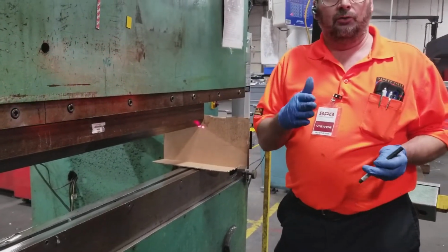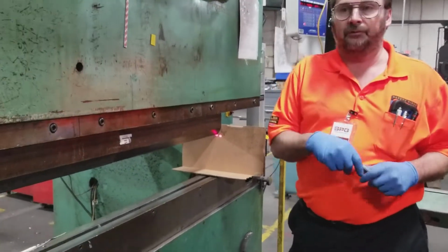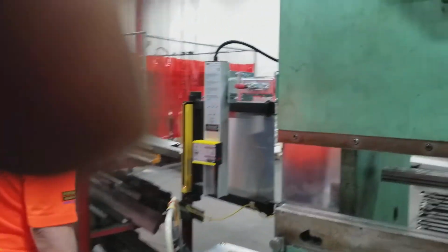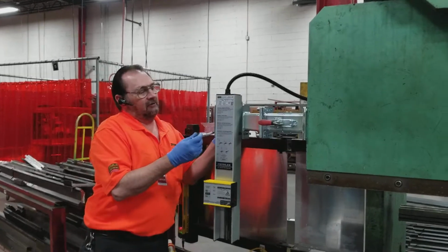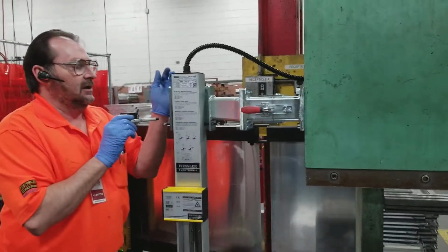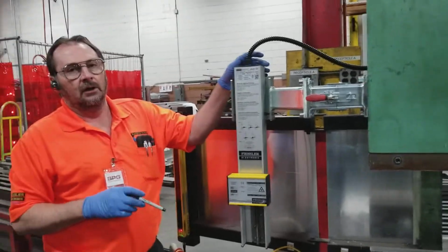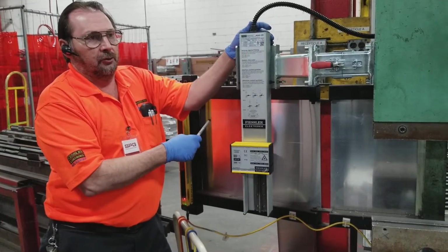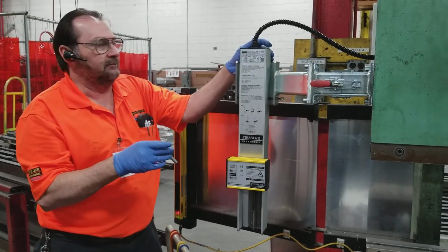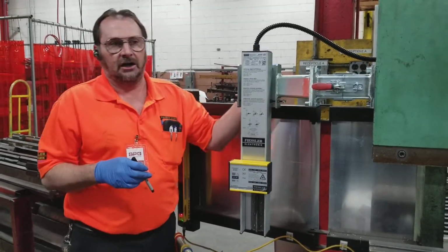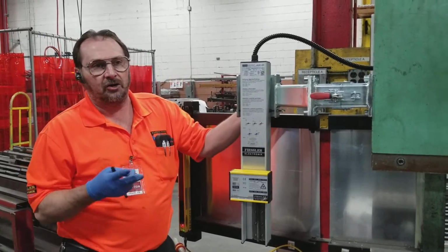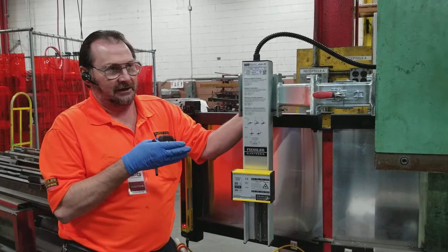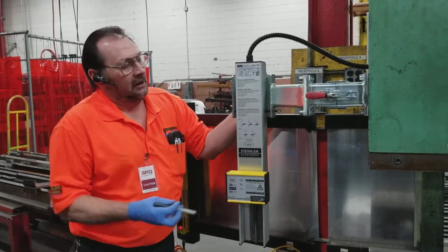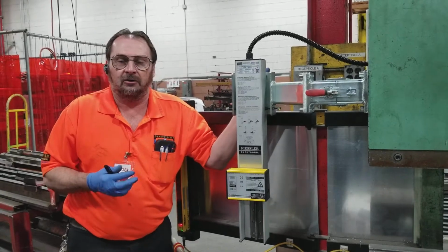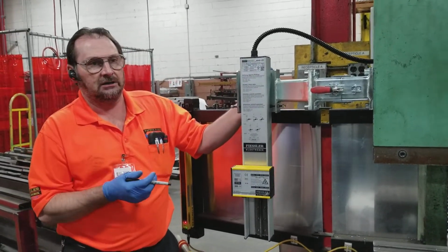If you have to do an alignment, we have 5 alignment bolts. 1 on the inside, 1 on the outside, and 3 in the rear. There's 2 on the top on this side, 1 on the bottom on the rear. On the other side, it may be the opposite. You also have 2 lockdown nuts in the back. The lockdown nuts are 13 millimeters, so you'll have to loosen them a little bit to get it to give. The alignment bolts have locking nuts on them also that are 10 millimeters, so you'll loosen those locking nuts.